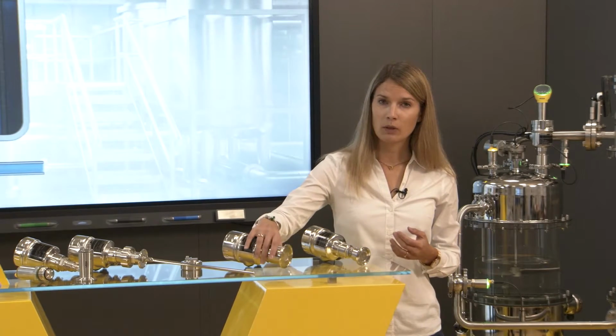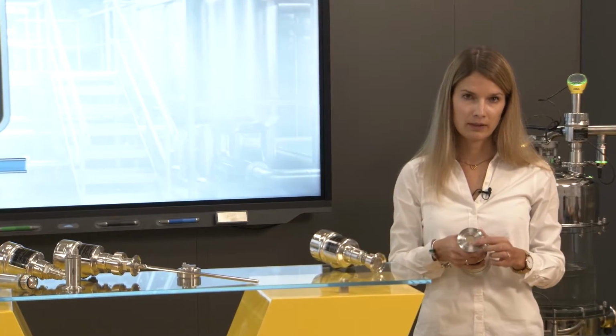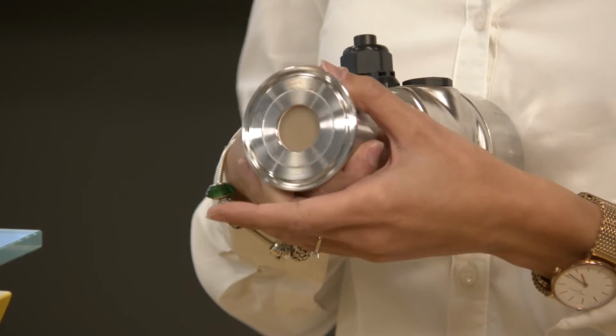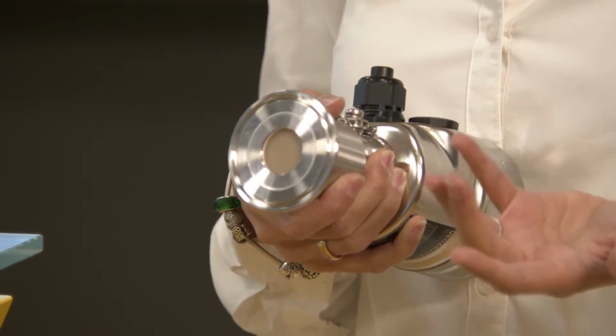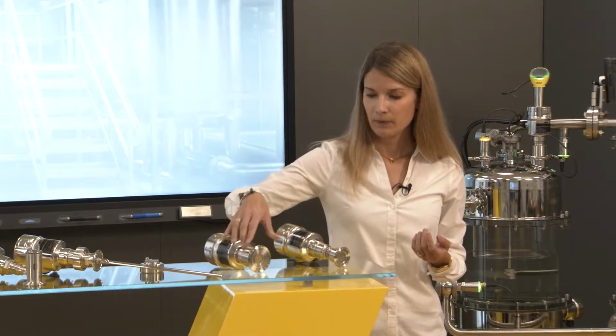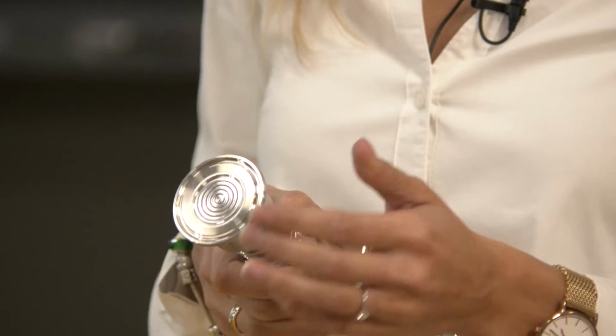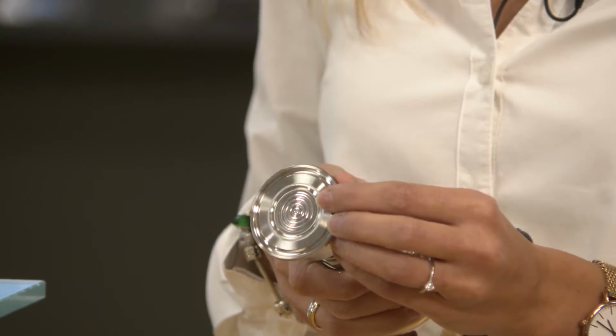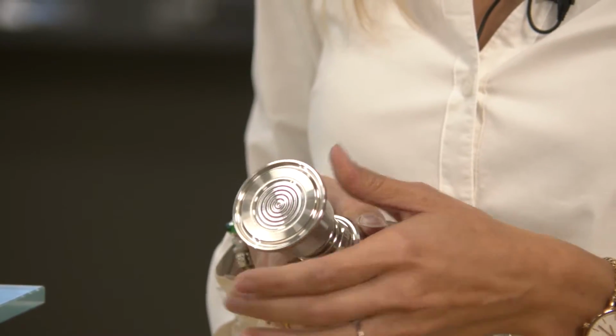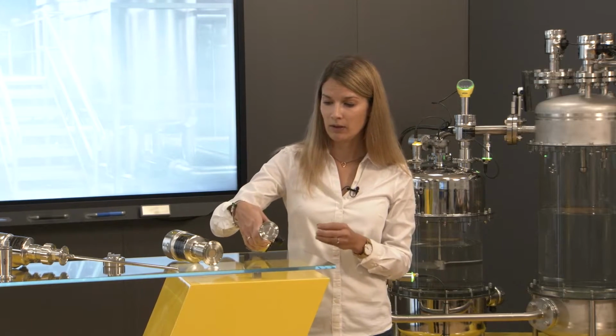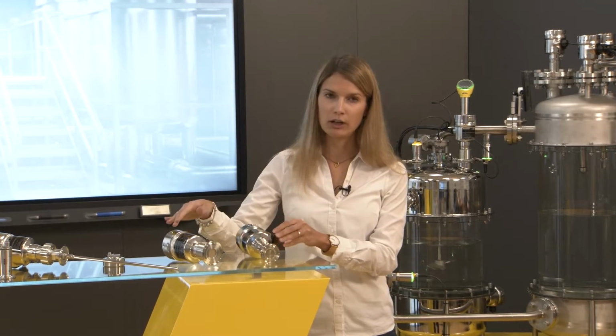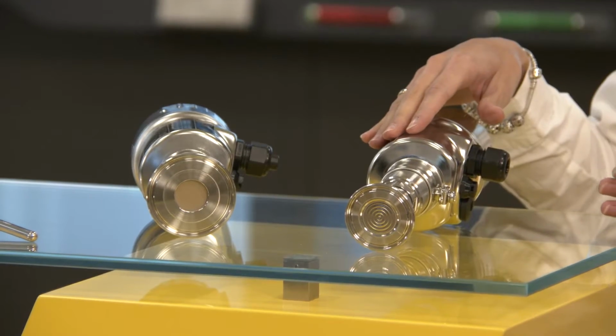Another big advantage is that you are very flexible in the selection of different versions. On the one side, you can use a sensor with a ceramic cell, with an O-ring inside of the process connection, especially when we have very abrasive media. Or on the other side, if it should be very hygienic, completely stainless steel, we have the metallic cell on the pressure device where there's no O-ring included, so this also means no O-ring has to be exchanged. And they can even be combined together in the electronic differential pressure system, a ceramic and a metallic version in combination.